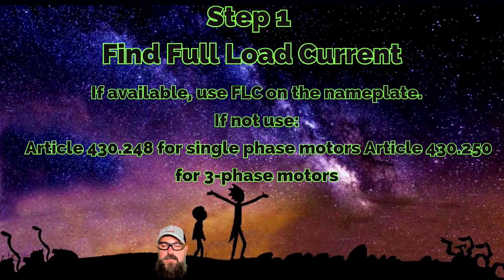Of course, if available, you're going to use the FLC on the nameplate. But for testing purposes, they usually don't give you that nameplate, so you got to figure it out. But as long as you have the voltage and the horsepower, you can find the full load current. So we're going to use Article 430.248 for single phase motors, and we're going to use Article 430.250 for 3-phase motors.